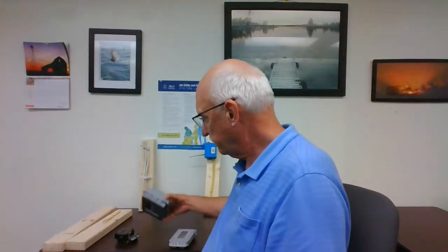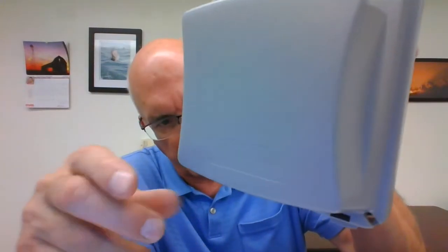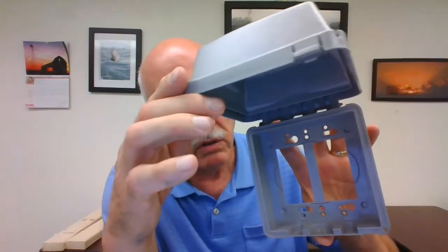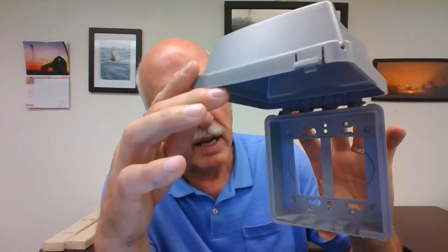For a damp location under a soffit, the old-style flip cap, the old-style garage door flip cap type can be used. The newer covers are the ones that are... I have two types of covers here. Whatever cover you use has to be marked as extra duty. It says extra duty right here. It's hard to see. Okay, but this type, whether or not the cord is plugged in, you would be able to close the cover on this type.